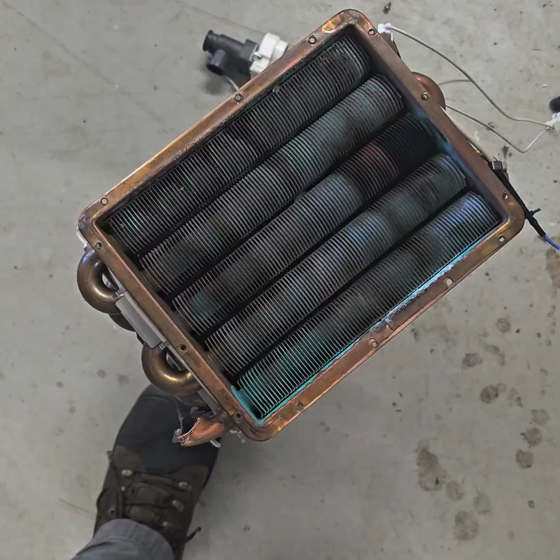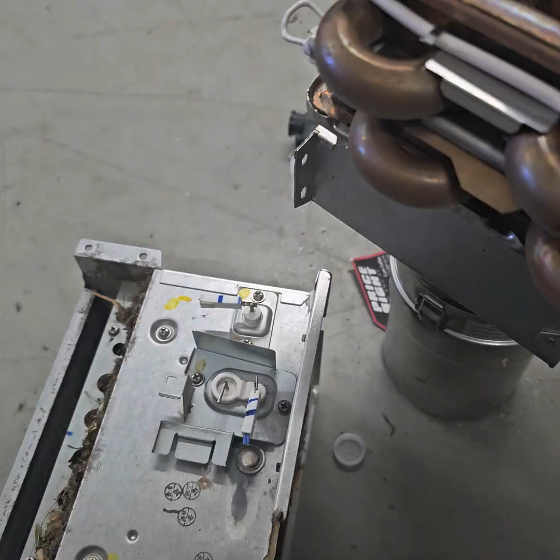So this is our heat exchanger. That is what's getting superheated during the time that your system is on and running. And as you can see, we have some areas of superheating where it's being overly heated. Secondly, this is the portion of the heat exchanger where the flames come out. Okay, as you can see, some of these very, very fine holes can get plugged, and I'll show you that a little bit more in detail here in a moment.